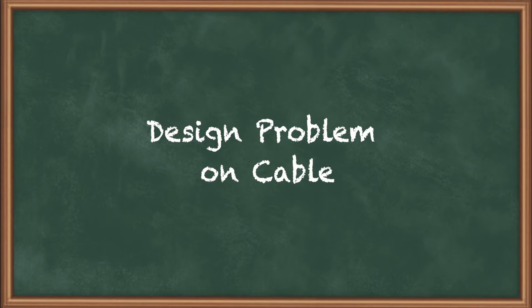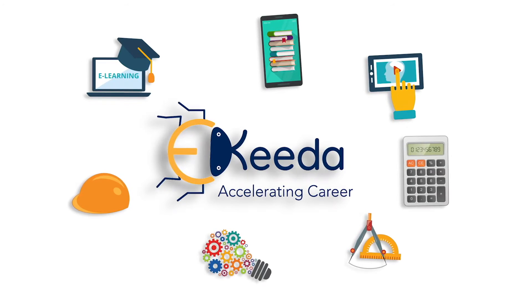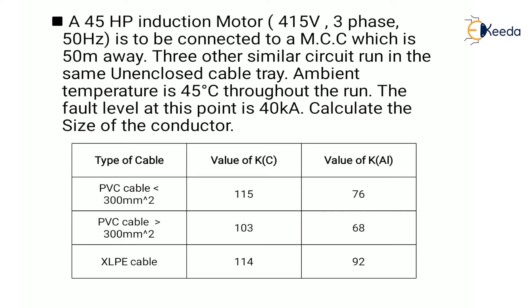Hello everyone, let's start with the next topic which is a design problem on cable. A 45 HP induction motor, 415V 3-phase 50Hz is to be connected to a motor control center (MCC) which is 50 meters away. Three other similar circuits run in the same unenclosed cable tray. Ambient temperature is 45 degrees throughout the run. The fault level at this point is 40 kA. Calculate the size of conductor.